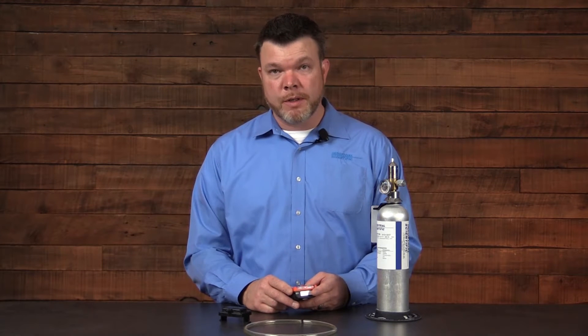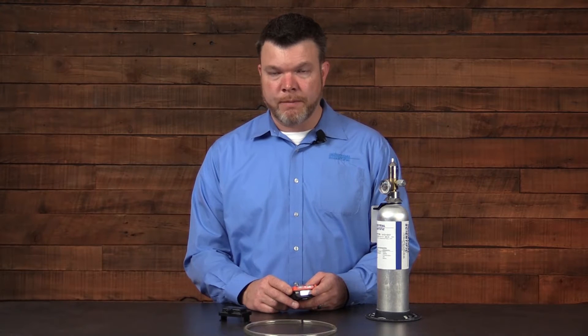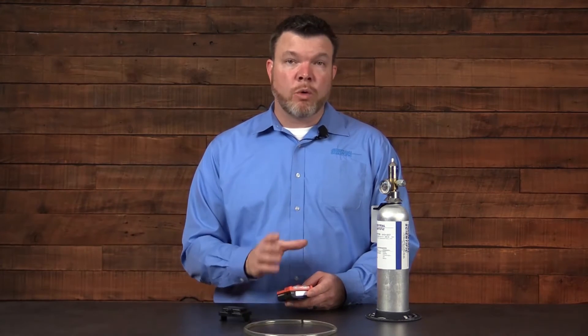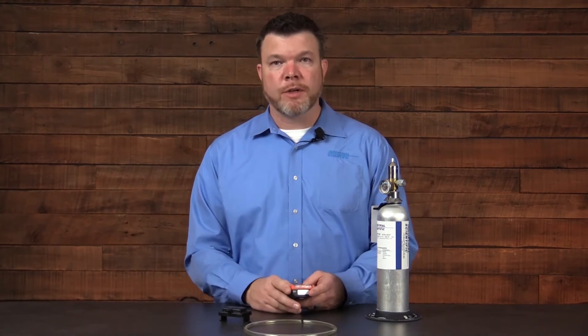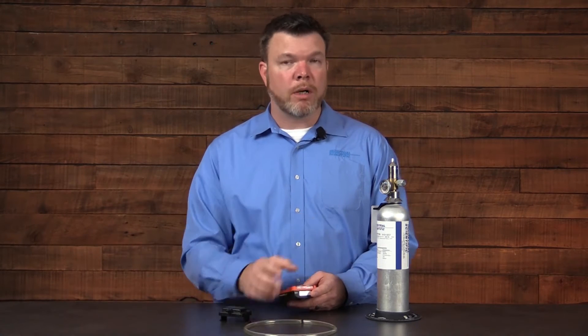The bump test for the Ventis Pro Series instruments is one that should be completed prior to each day's use. The test I'm going to demonstrate today is one of the quick variety. You have the standard and the quick variants for your bump tests and your calibrations. Because all of the contents of the cylinder are in one bottle for my instrument, I can select the quick variety.